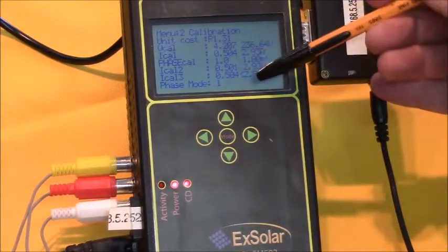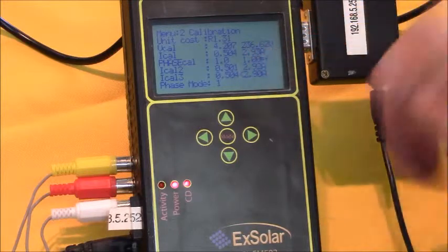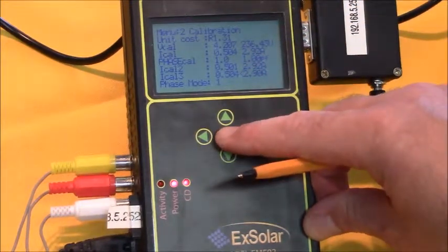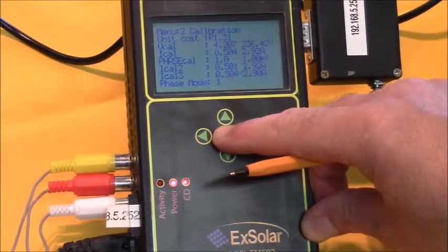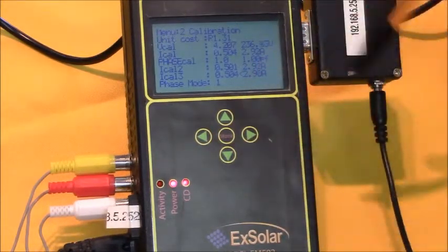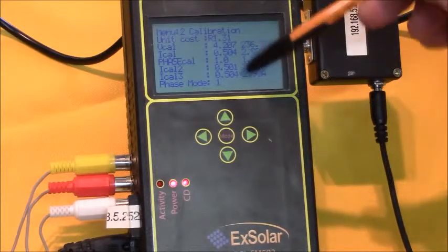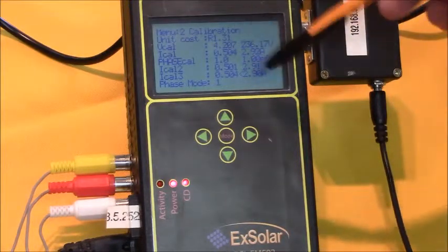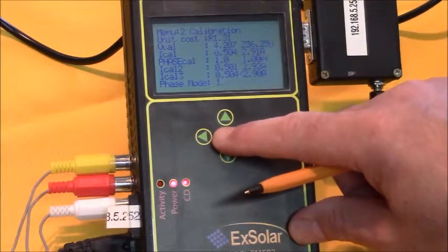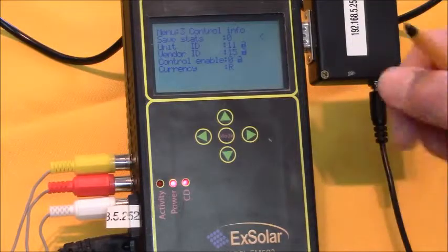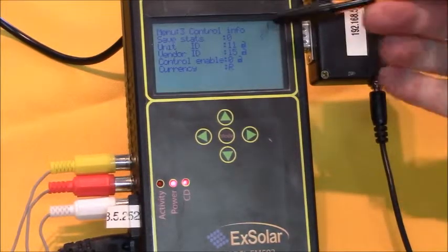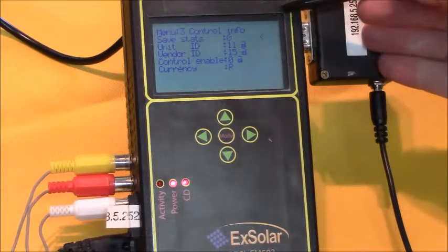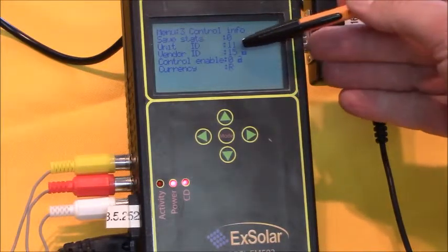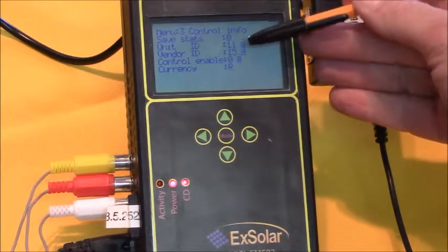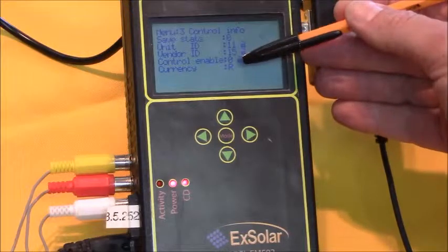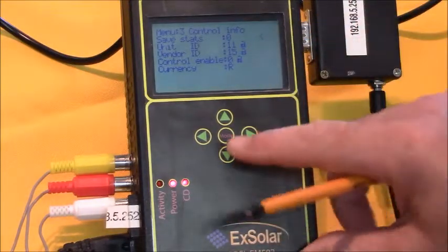Once you have finished the calibration procedure, the data values are only stored when you push mode for the second time. So if at some stage this unit was powered off before you change from this screen to the next screen, then you have to go through the whole calibration procedure again. So after calibrating, just push mode again and all the values have been saved. This screen is basically used in the workshop for changing the vendor ID and unit ID and some other details which we use for the configuration of the energy monitor. It's not user settable.